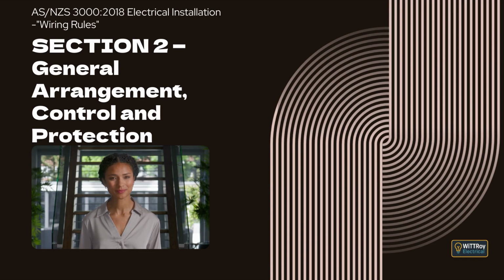For normal installations, this space is at least 1 meter from the face of the board. In a domestic installation, this can be reduced to 0.6 meters from the front. Around switchboard doors, we need at least 0.6 meters of clear space so the doors can open and close safely. No one should be forced into the switchboard or trapped by a door. This is especially important when the doors open into passageways or narrow walkways.